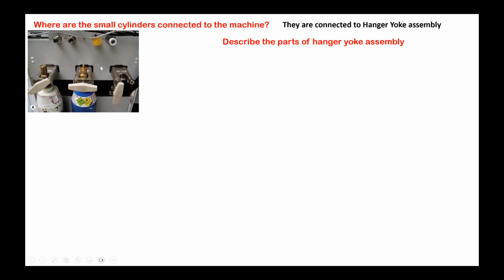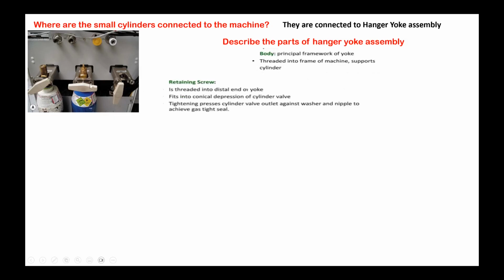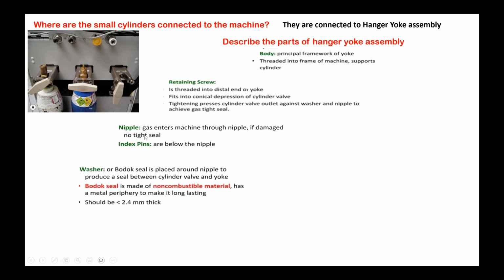These are all very basic questions. The body is the principal framework and is threaded into the machine. Then there is a retaining screw, this white thing, which is threaded to the distal end of the yoke. Then there is a nipple, where the opening in the cylinder will fit. It has index pins here. Then there is a Bodok seal. So you must remember all the parts: body, retaining screw, nipple, and Bodok seal. And a filter is also there, which is not visible.